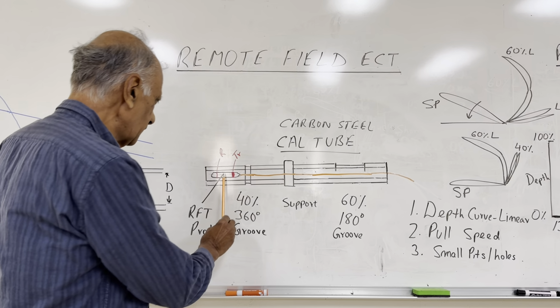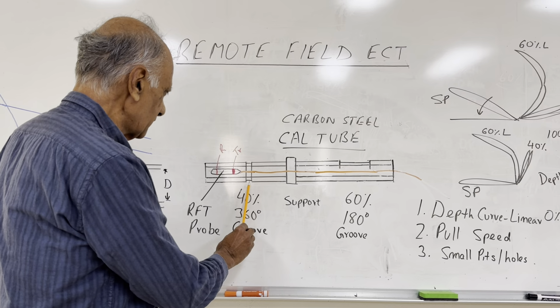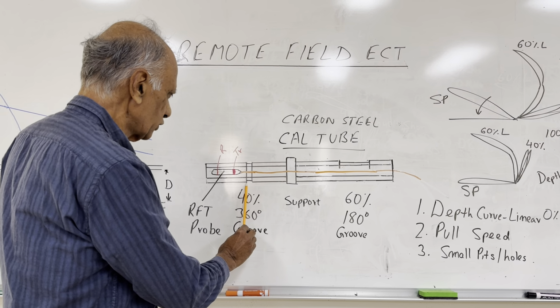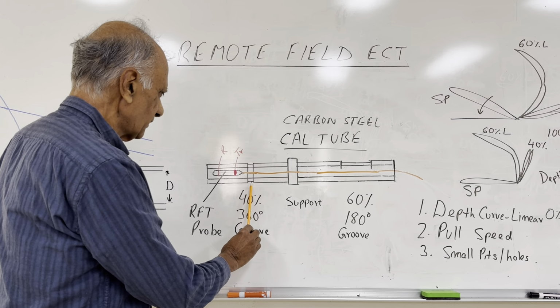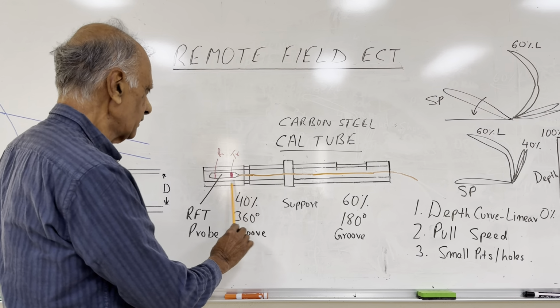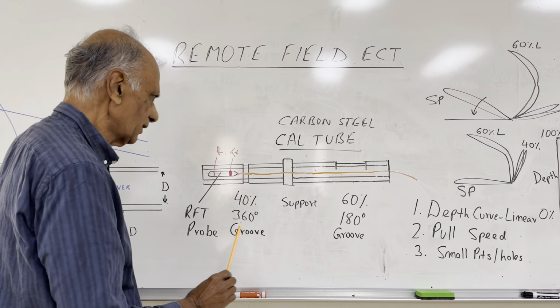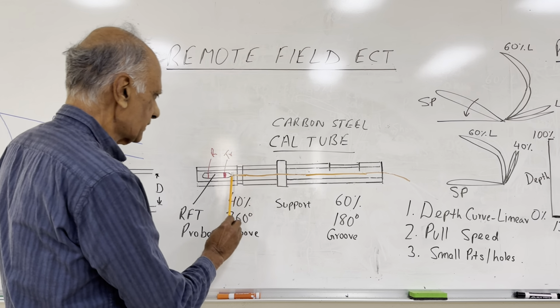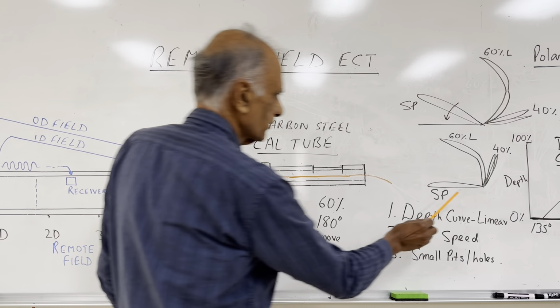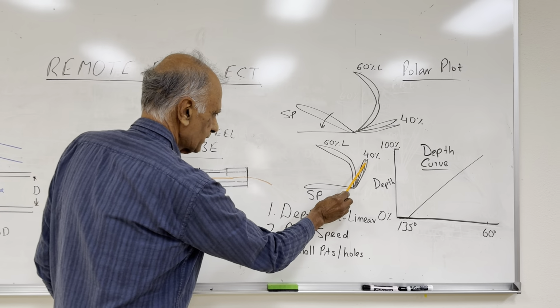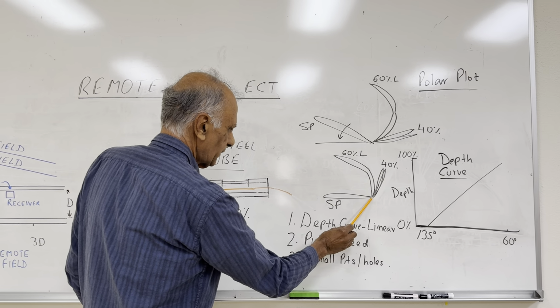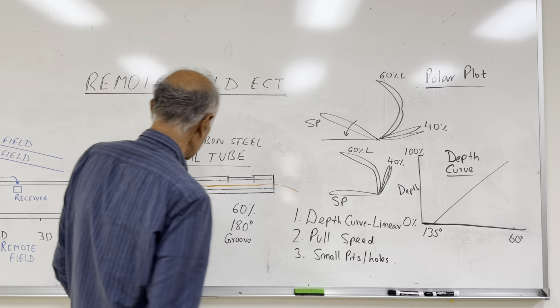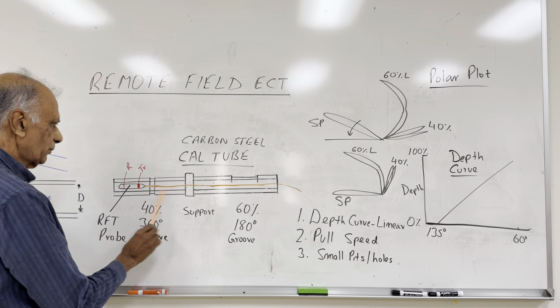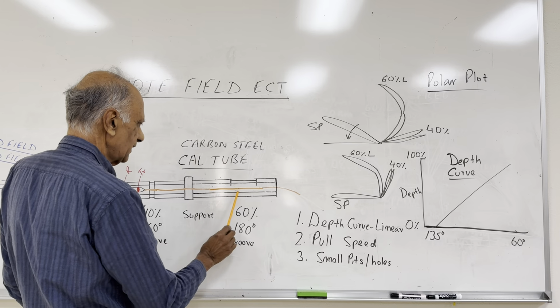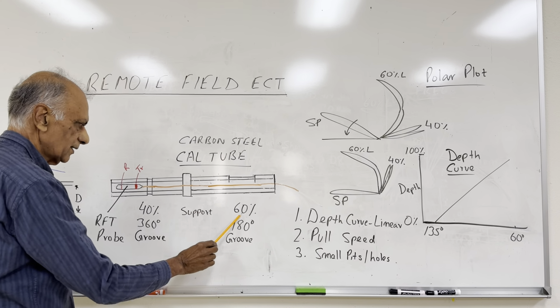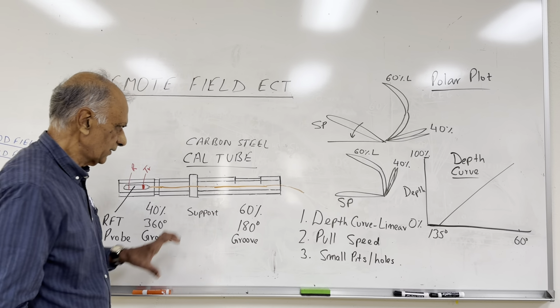So when we pull the probe here, it's going to see this small groove, which we call the short, which means that the groove length is smaller than the spacing between the transmitter and the receiver. So when you pull the probe, you will see this groove two times, which is here and here. So first the transmitter, and then it goes back to the balance position, then the receiver, which is the second signal, and then we are going to see the support plate, and then we will see the long groove, which is 60% and 180-degree groove.